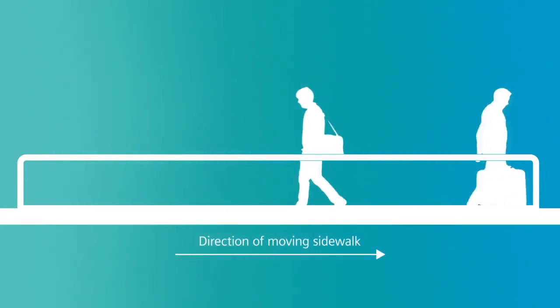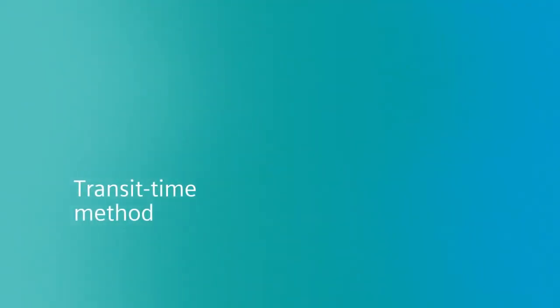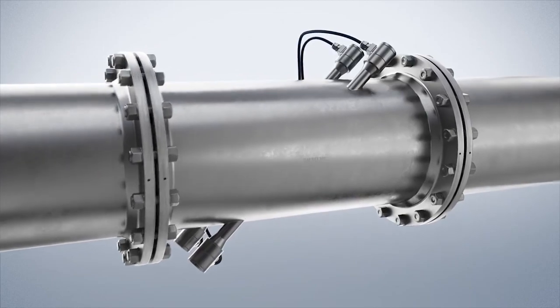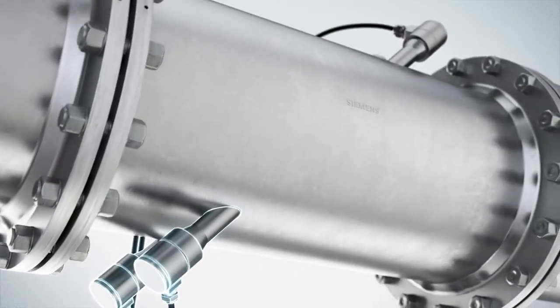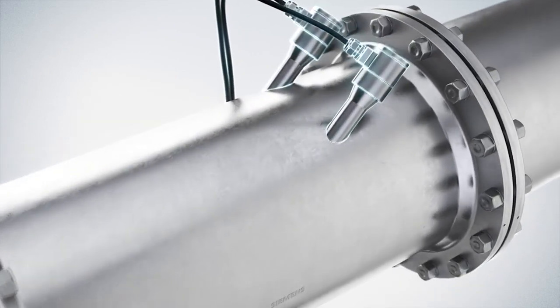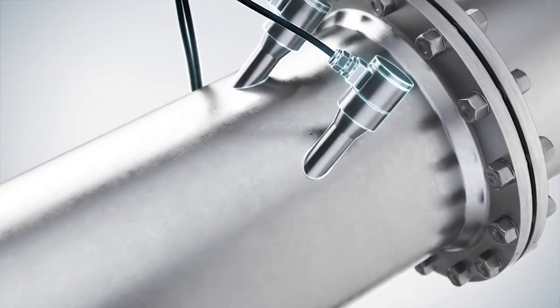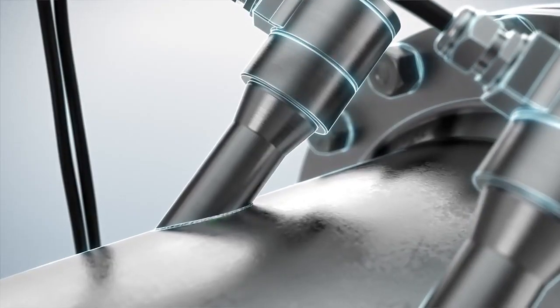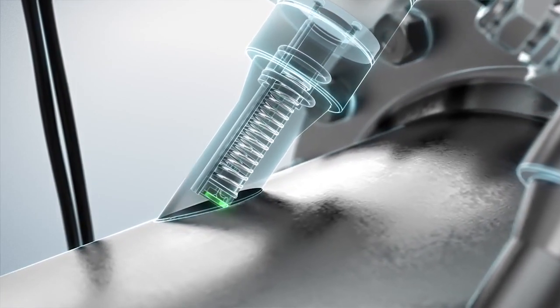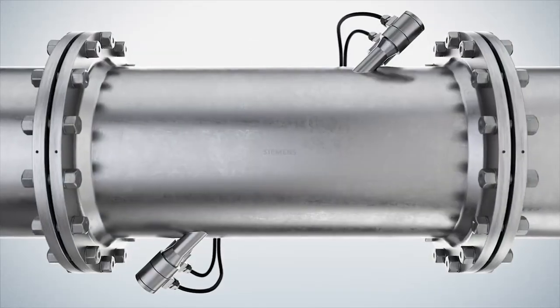In a flow system, sound waves behave in the same manner. Combined ultrasonic transmitters and receivers are placed opposite each other. Ultrasonic waves are alternately sent and received by means of the piezoelectric effect, where mechanical energy is converted into electrical energy through the use of a crystal.